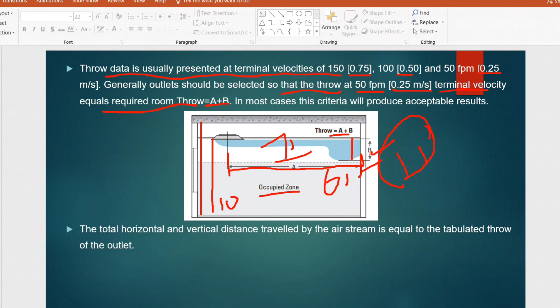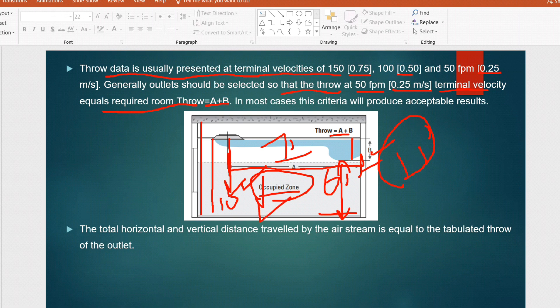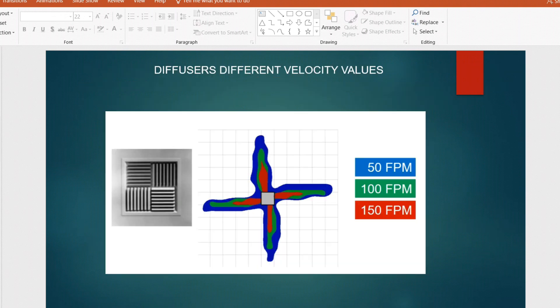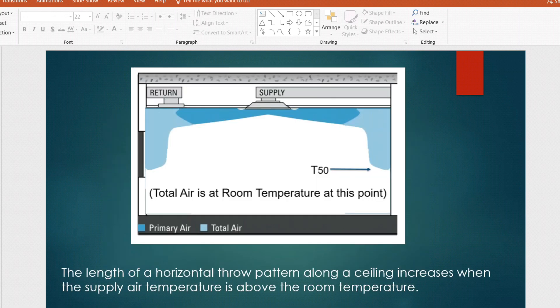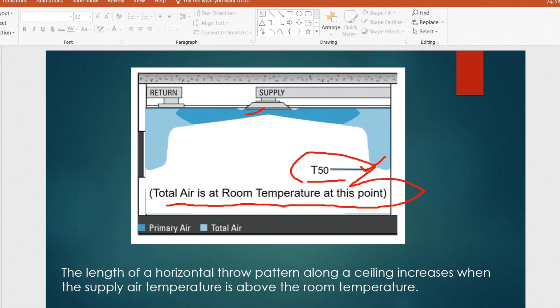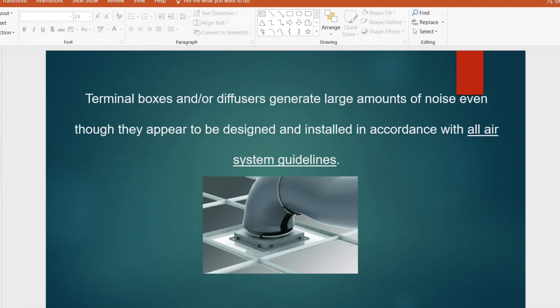The concept is that the diffuser should not throw air directly into the occupied zone, which would be uncomfortable. The occupied zone is defined as the 6-foot zone from the bottom floor level. Air diffusers are designed so the blades throw air to both sides. We select at 0.25 m/s terminal velocity because the air coming from the diffuser is at very low temperature, and at this point — 50 ft/min — the total air has reached room temperature. This is why the selection is based on 50 ft/min.